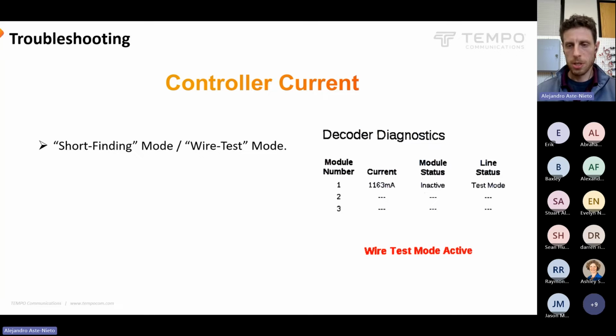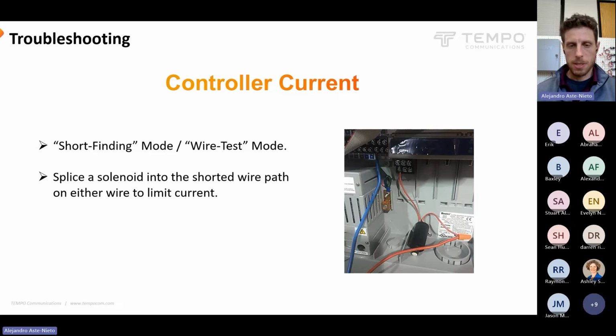If the controller refuses to run with a short in the field, even on short finding mode, one thing we can do is splice in a solenoid to one of the 2 wires coming from the controller, and that will add enough resistance to where it can now give you some current from the controller safely.